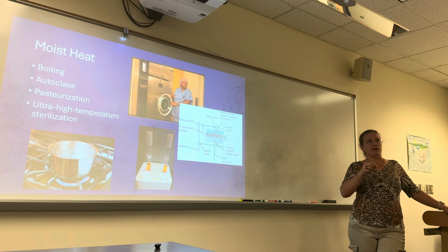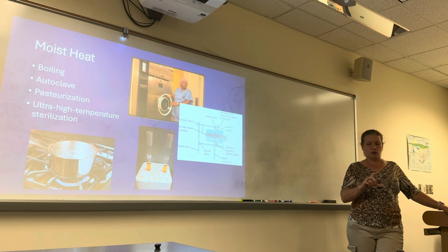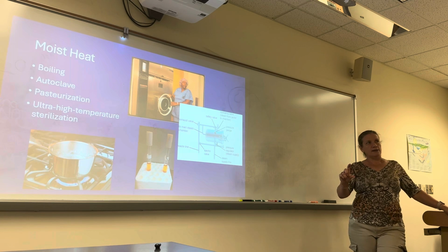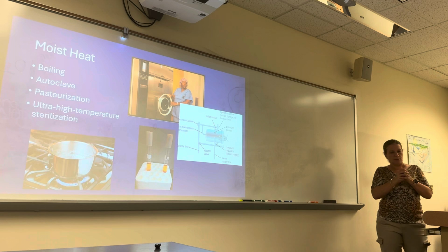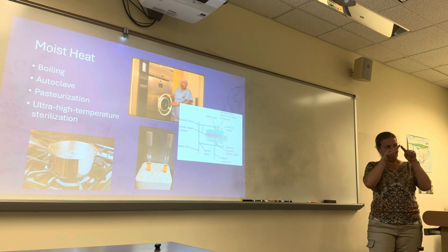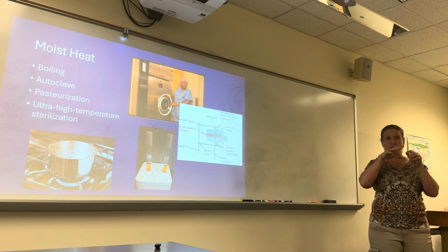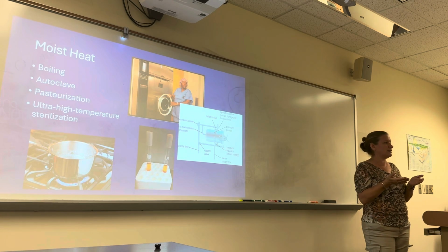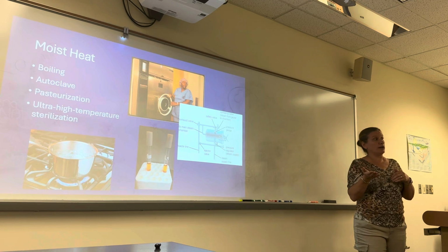The endospores are in a media, so you put the little ampule in and autoclave it. Then when you take it out, you squeeze the ampule to break the media. The media is in a separate little ampule inside, and squeezing breaks it, releasing it so that it has contact with the endospore strip, and you incubate it overnight.